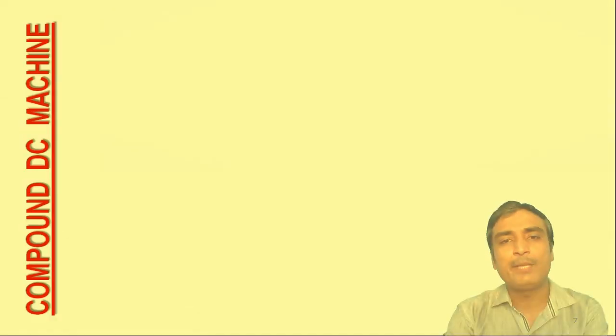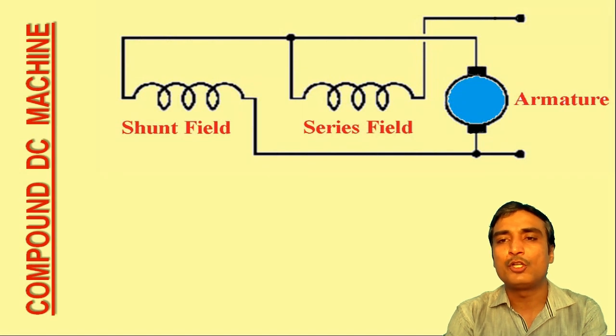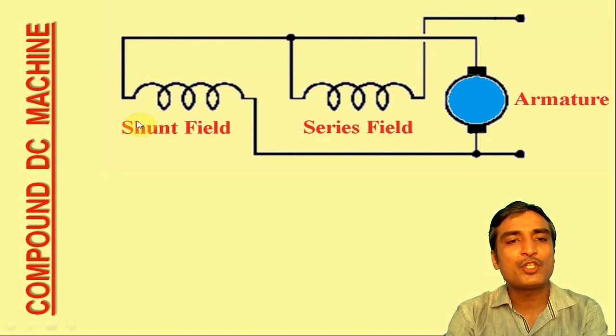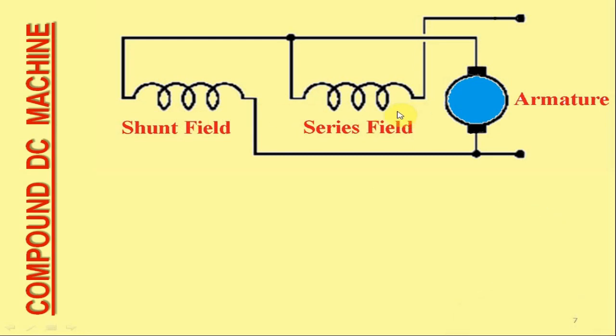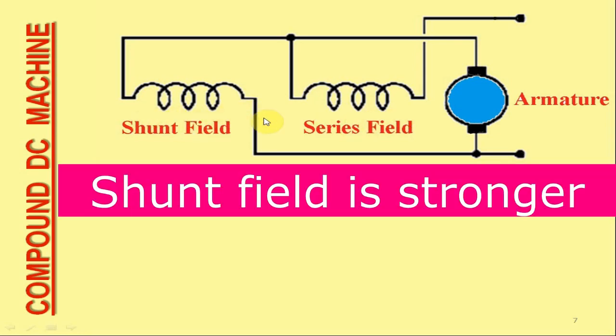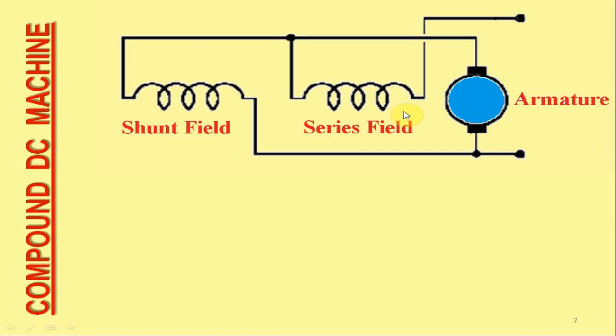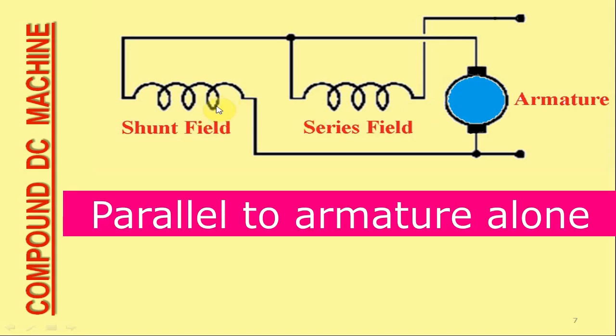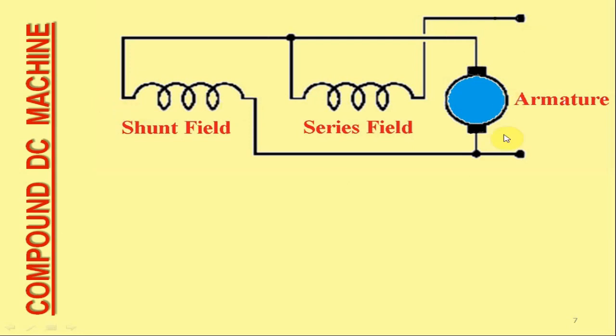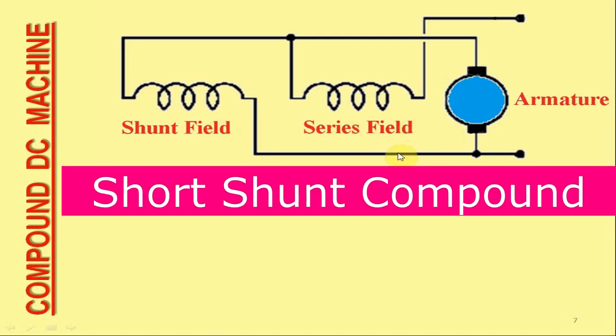Next is the compound DC machine. As you may see in the typical representation illustrated on your screen, a combination of both the shunt and series field excitations are provided. However, in a compound DC machine, the shunt field is substantially stronger than the series field. Notice that in this typical arrangement, the shunt field winding is in parallel with the armature alone. With this sort of field winding arrangement, the machine is called a short shunt compound DC machine.